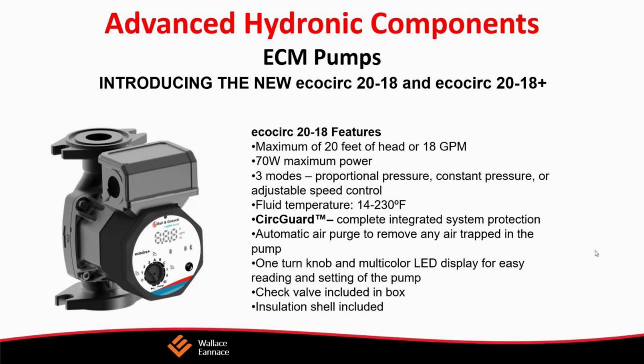So how do we improve that? If we substituted small EcoCircs, these smaller pumps, they can be set to draw as little as 10 watts. So their efficiency is almost 10 times greater. When you consider that, the distribution efficiency would be 400,000 BTU divided by 40 circulators at 10 watts, which produces 1,000 BTUs per hour per watt. It's a tremendous increase.